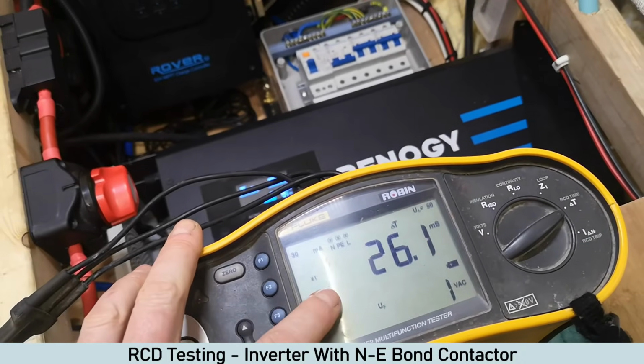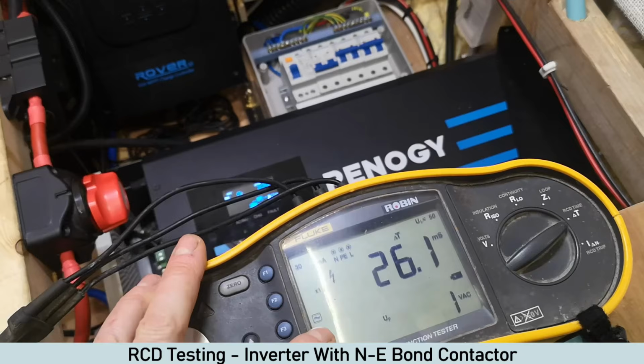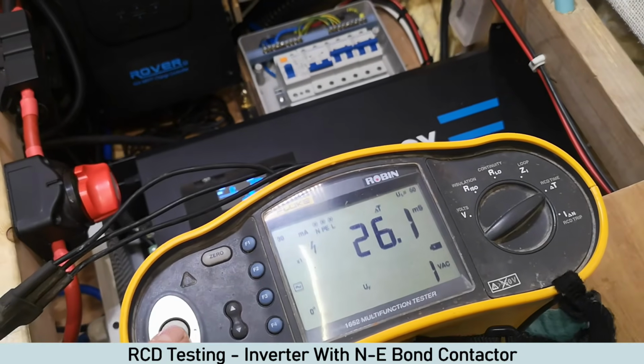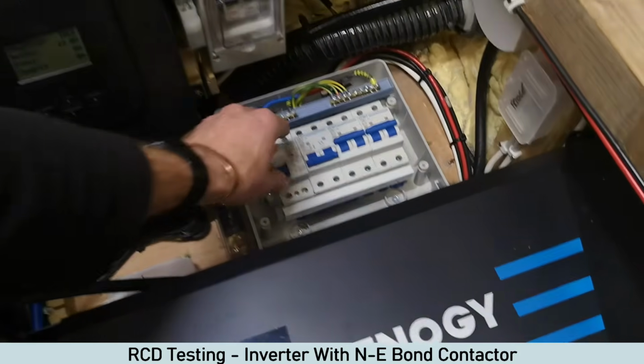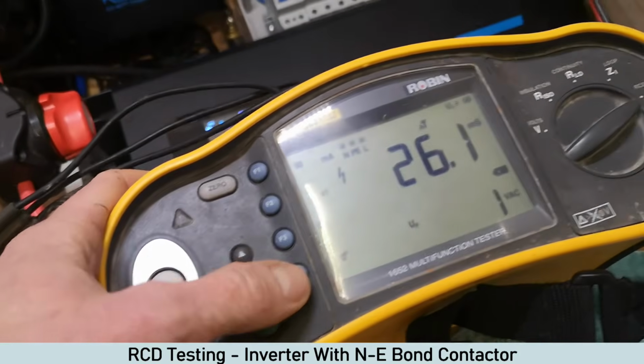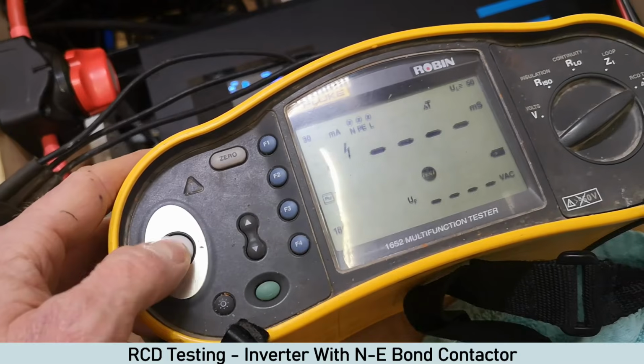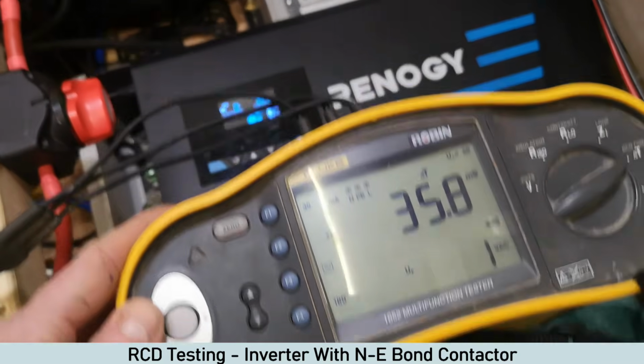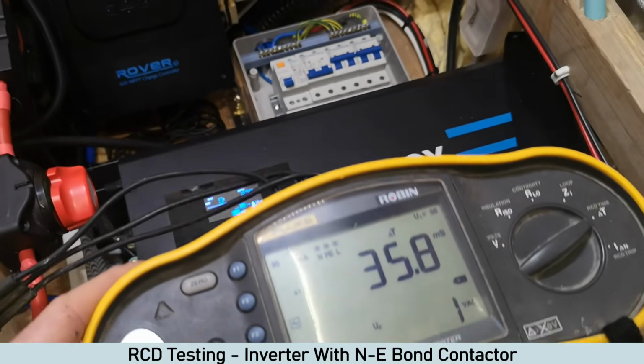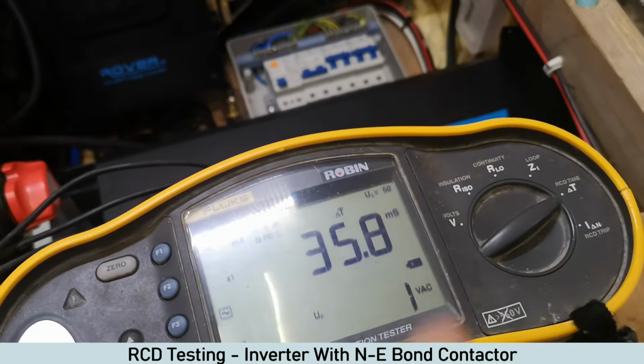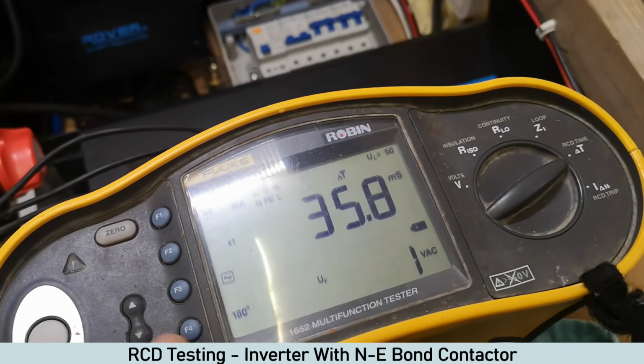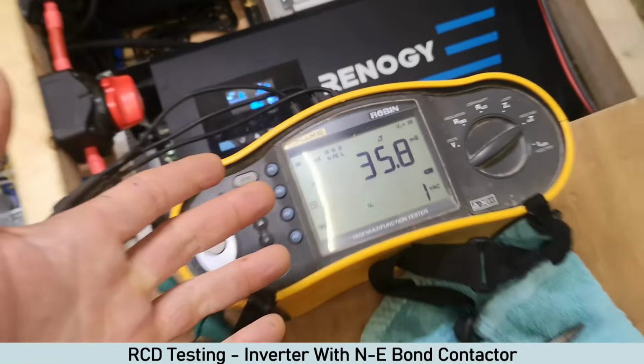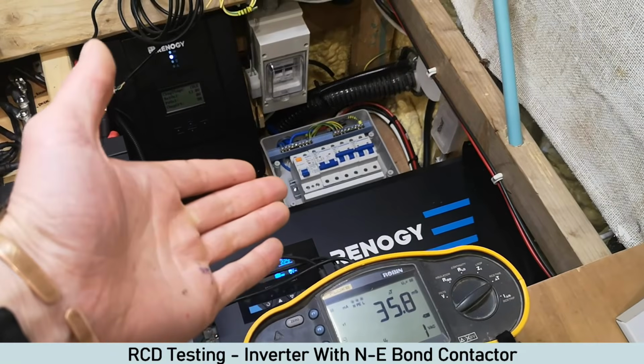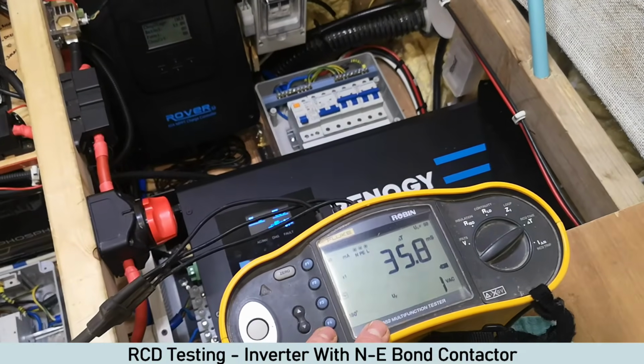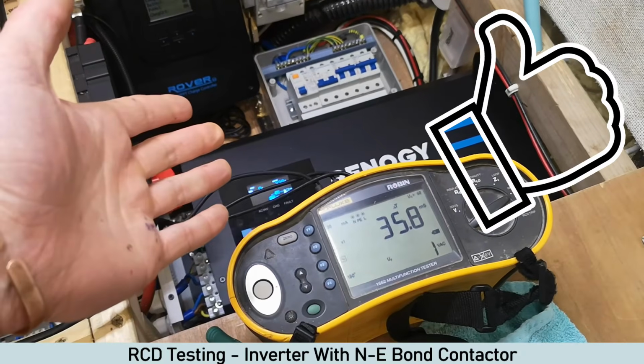So I've got it set to 30 milliamp, trip at 1 times, which is fine, and set to AC. So if I hit that, boom, tripped. What I'll do, I'll just test it the other way as well. Boom, happy days. So the reg states it's got to trip in less than 300 milliseconds, and you can see there, 35.8. But that's just proved that that RCD is testing, and that test is to the regulations, so tick.